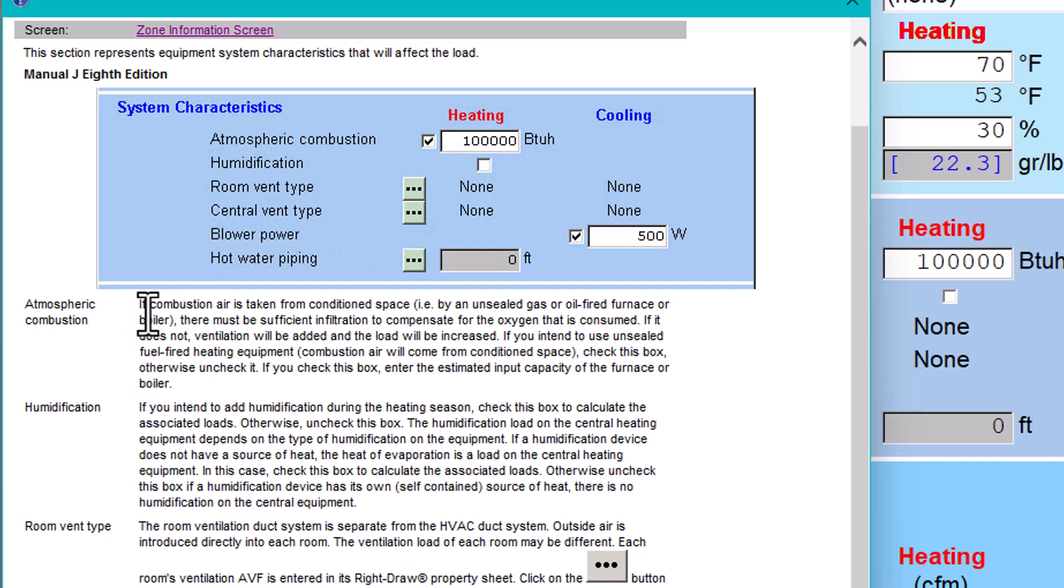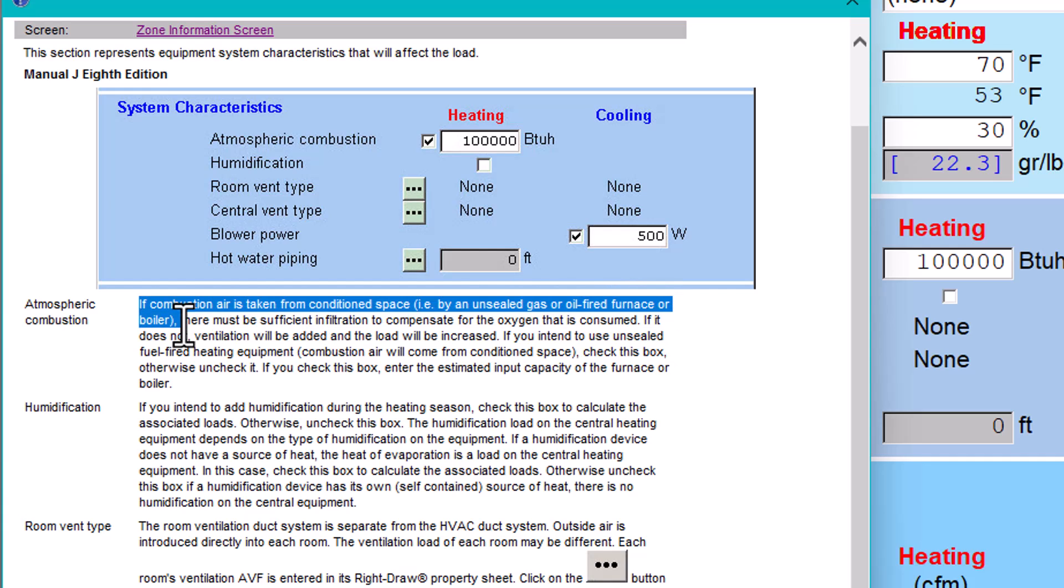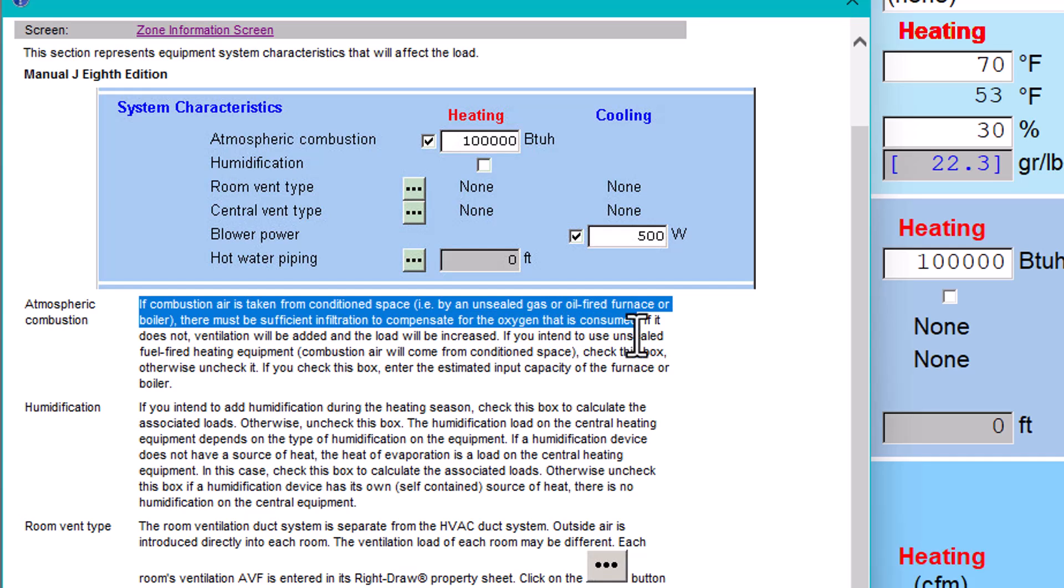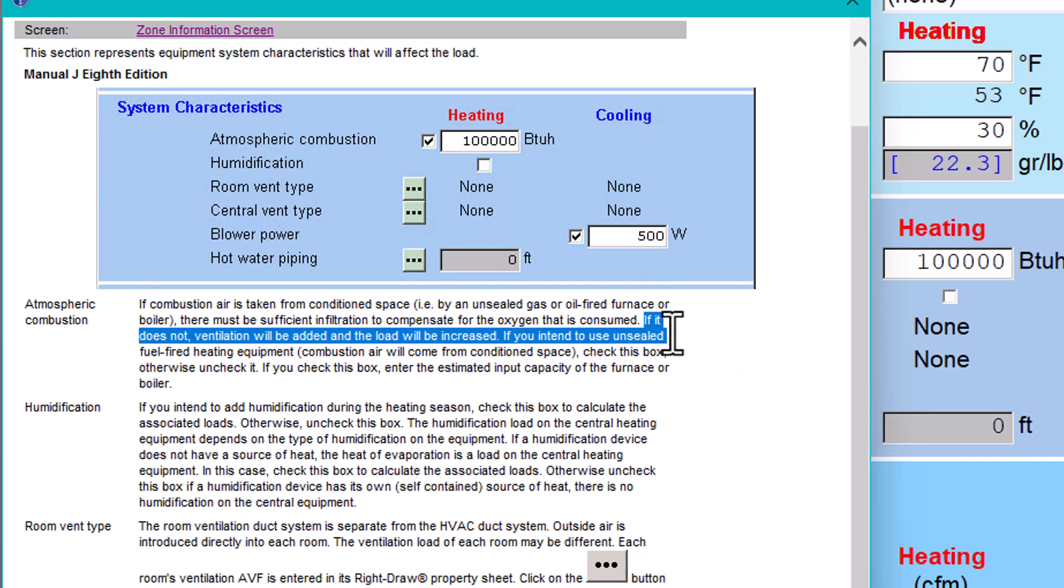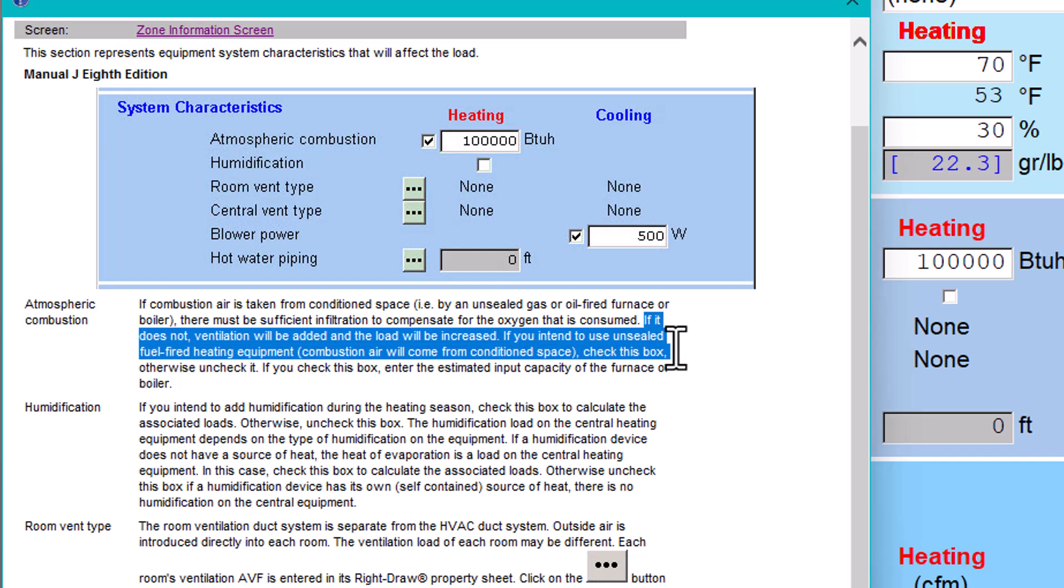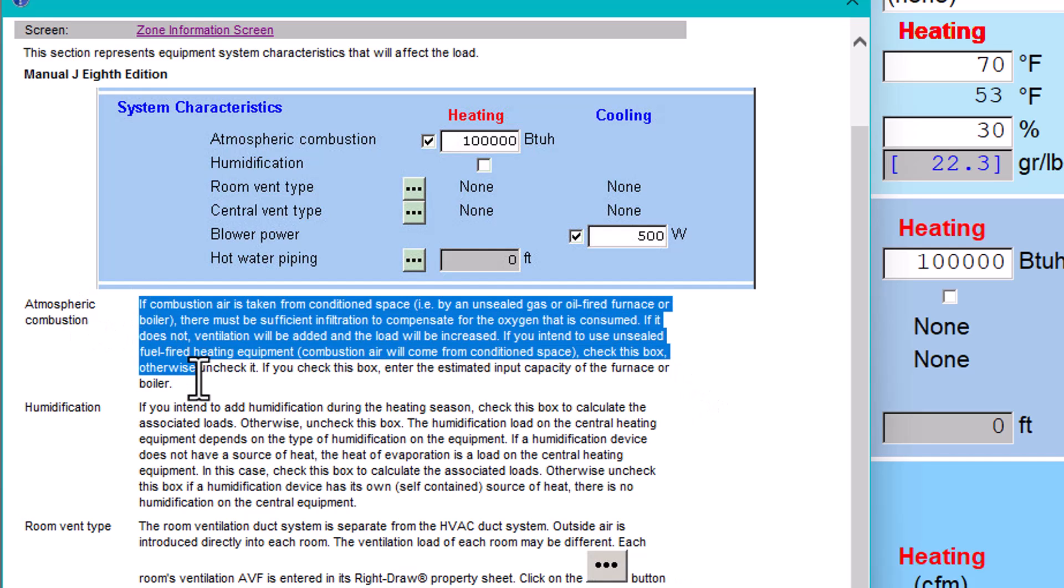So you click on that and you're going to be able to find the explanation for atmospheric combustion. Let's just read through it. It says if combustion air is taken from a conditioned space, for example, by an unsealed gas or oil fired furnace or boiler, there must be sufficient infiltration to compensate for the oxygen that is consumed, which is right. So if you have a furnace in your basement, you need to do a calculation to bring air. They need oxygen for the process to work. So if it doesn't, ventilation will be added to the load and it will be increased. So if you intend to use unsealed fuel fired equipment, combustion air will come from conditioned space - check this box. Otherwise, uncheck it. If you check this box, enter estimated input capacity of the furnace or boiler. So you have the explanation in here.